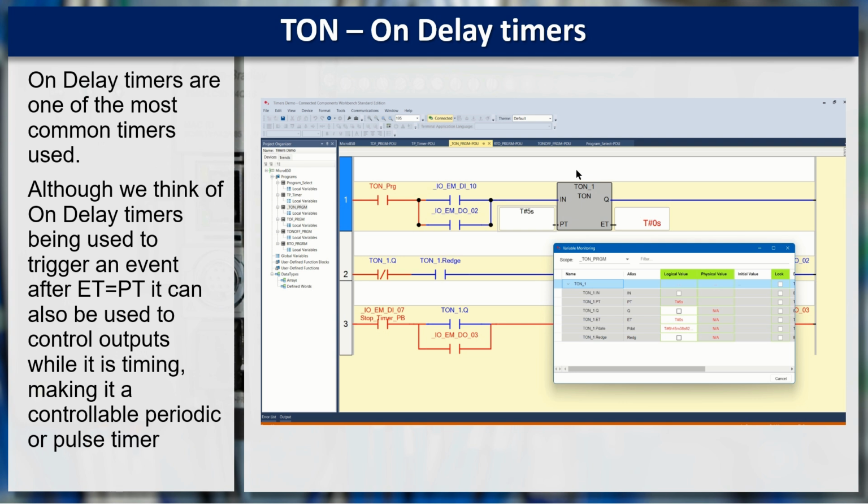When timers only had a tenth of a second and a second, or a millisecond and a second as its time base, you had those two choices. If you had it set to a second and your scan time is running at half a second, it didn't make any difference. It was not that sophisticated. It didn't matter. However, as the processors got faster, as the logic got interpreted faster, they were discovering very quickly that what would happen is the timers were not starting on time.